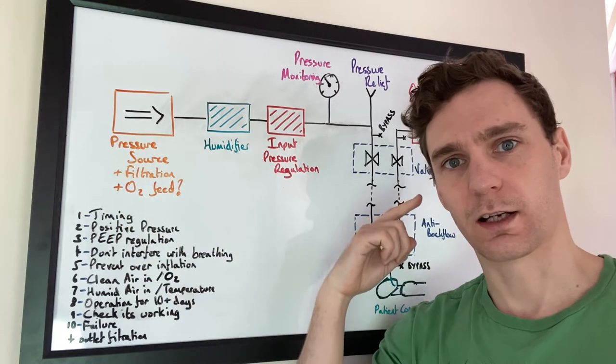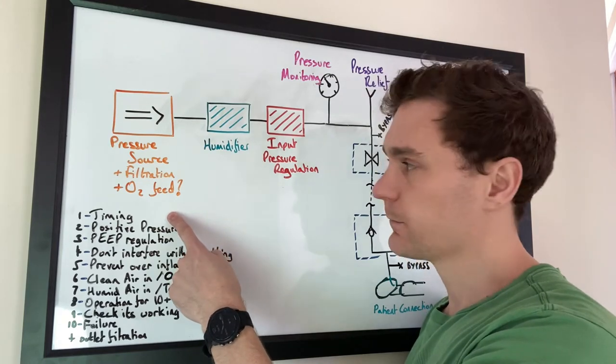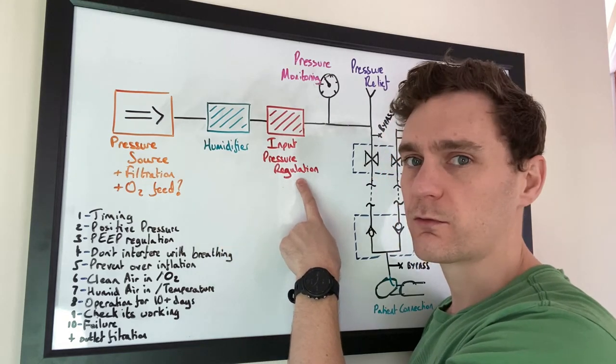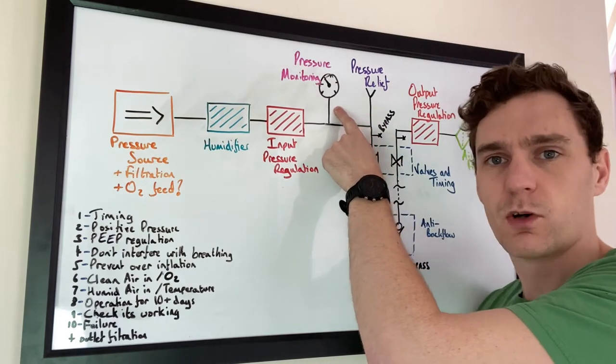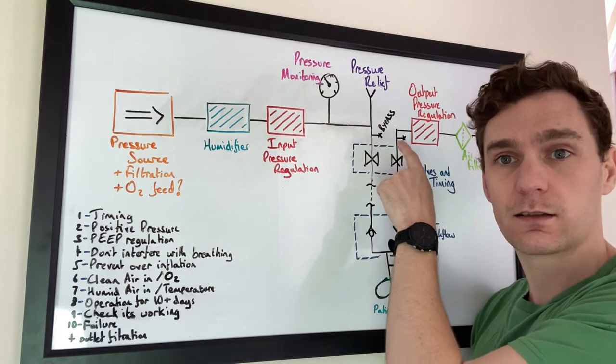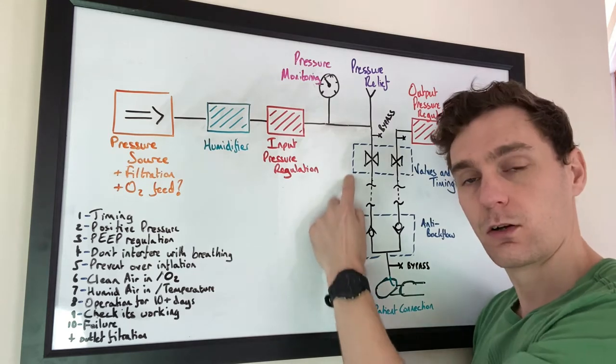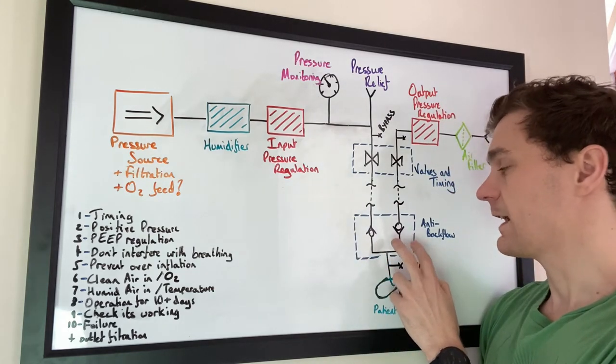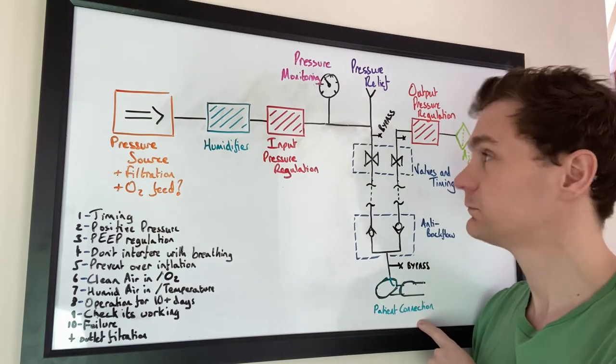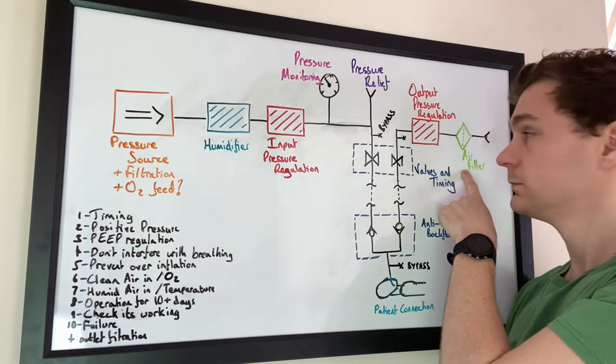So let's just start with a rundown of the whole architecture of the system. First off we have a pressure source here. There's also some filtration and possibly an oxygen feed. Next we have a humidifier. Next we have input pressure regulation. Here we have pressure monitoring. Pressure relief. We have bypass here so this is where you could connect another tube. We have the valves and timing. Here we have a long tubing run. Here we have the anti-backflow region. We have another bypass. A patient connection. Up here we have output pressure regulation. An output air filter. And then the exhaust.